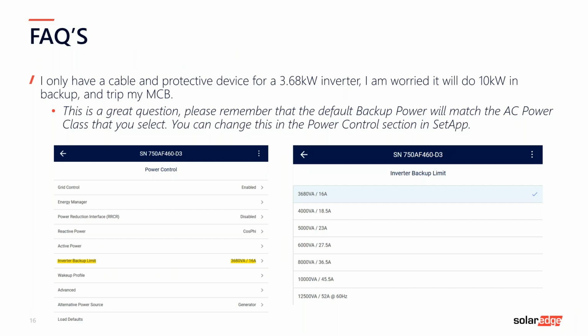Some inverters quote 8 kilowatts but can only supply 6 kilowatts. Yes, there's a difference between Home Hub and HD-Wave inverters here, but the multi-range concept inverter will give you a maximum of 10 kilowatts. If you have two batteries, you'll get 10 kilowatts of backup. If you've got 5 kilowatts of PV and a 5 kilowatt battery available, you will get 10 kilowatts in backup.